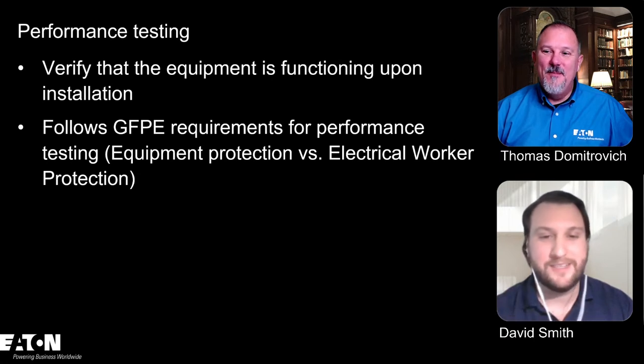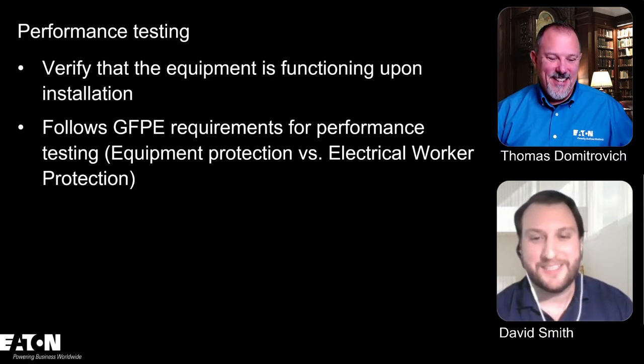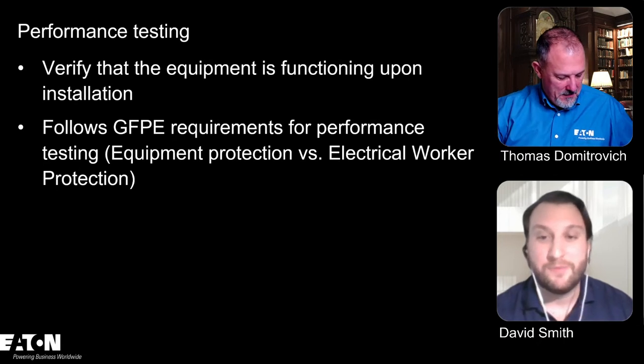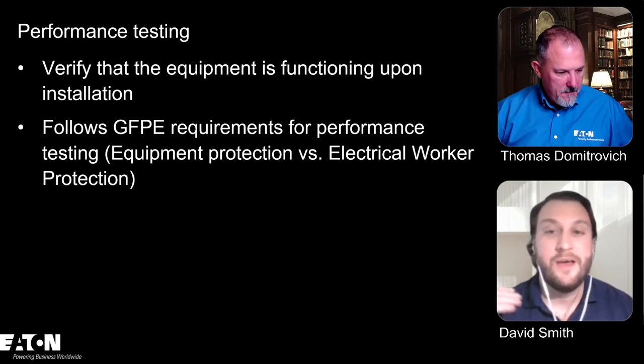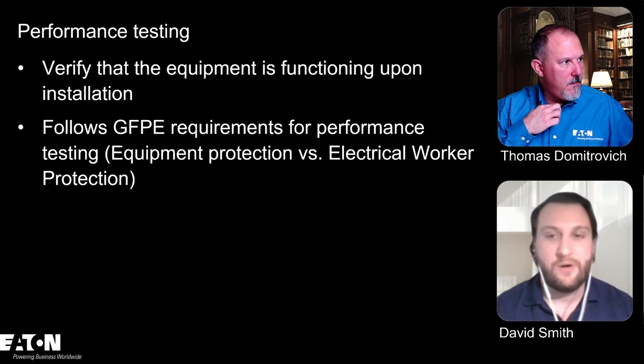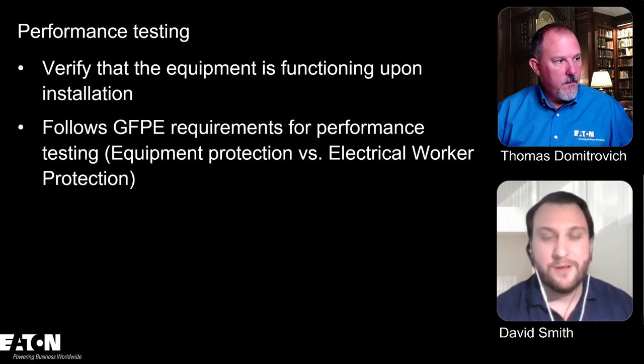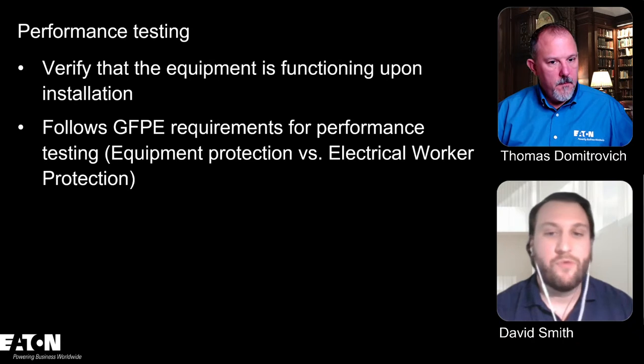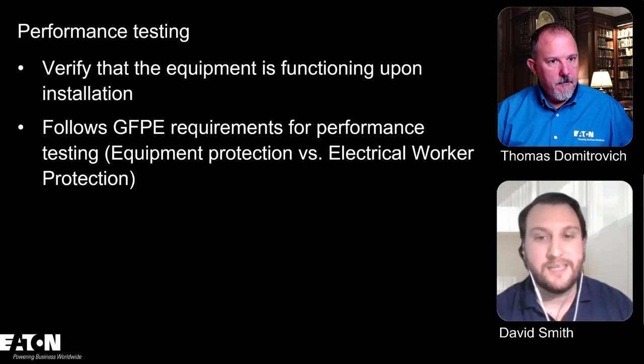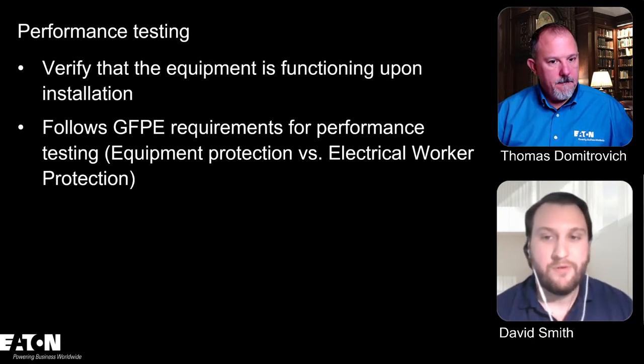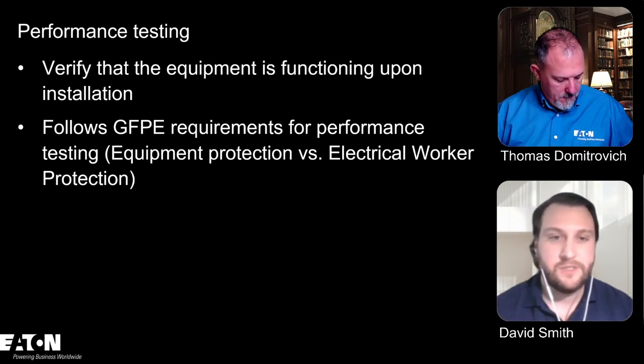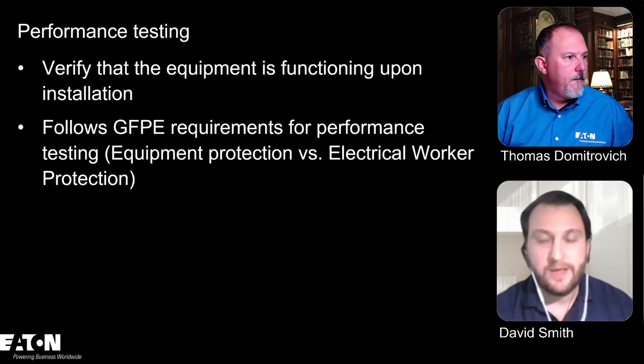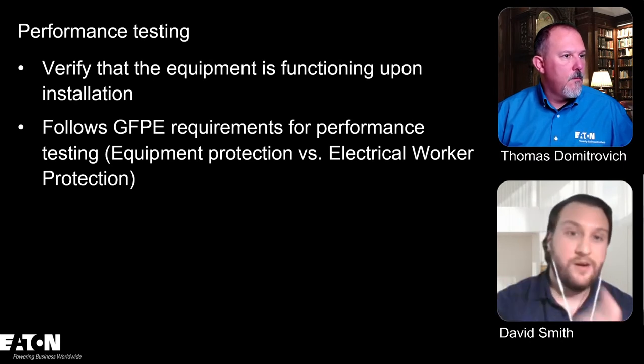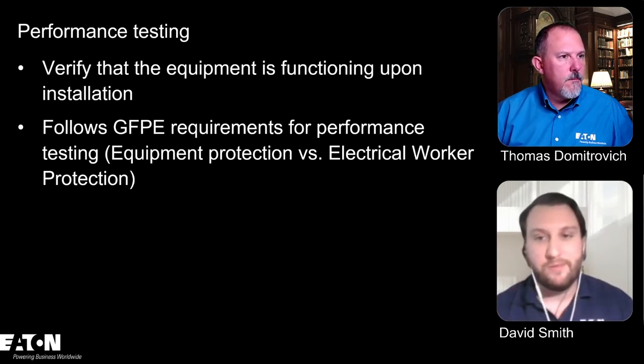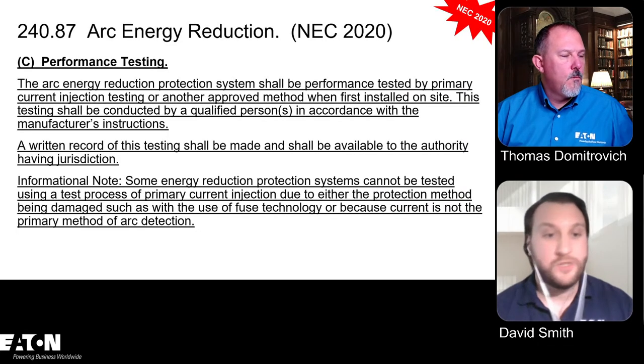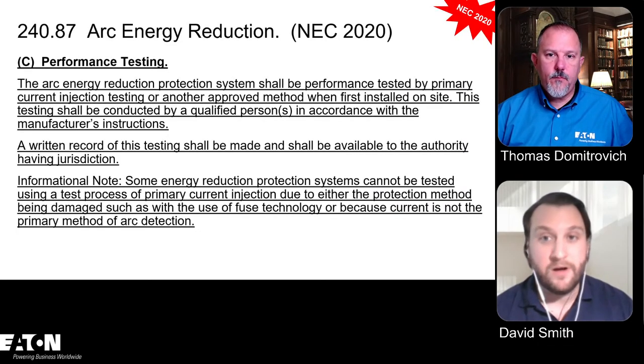Whenever I talk about this all the time, primary current injection. Thank you. I couldn't remember the order of the words. Primary current injection testing is the approved method that's specifically called out in the code. However, that particular sentence talks about performance tested by primary current injection testing or another approved method when first installed onto the site.